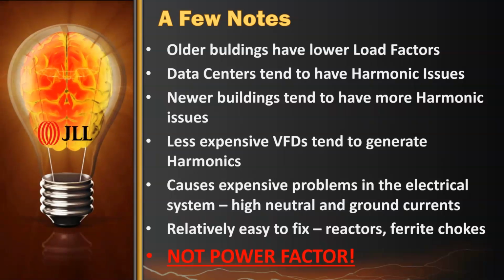So there's a few notes about this. Older buildings tend to have lower load factors, older office buildings and things like that. Data centers typically tend to have a harmonic issue. Usually it's because of the inverters, which generate a transient and a harmonic and various other things that are not very healthy. Sometimes the servers will do it themselves. That can be an issue as well.